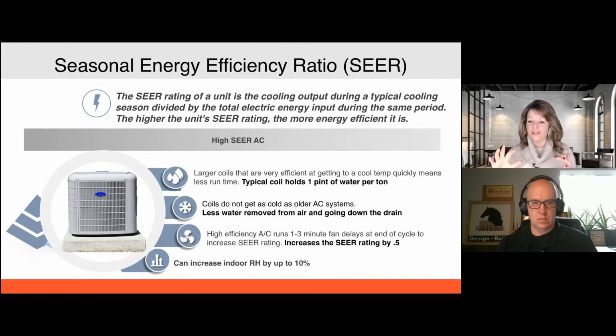And then they kind of cheat the system a little bit. When the compressor shuts off because the thermostat has been satisfied, the fan will run 1 to 3 minutes afterwards. By doing this, they increase their SEER rating by 0.5. So they're getting credit for evaporative cooling, because all the water that's left on the coils when the compressor shuts off is getting re-evaporated back into the living space. And that can increase the indoor RH by 10%.